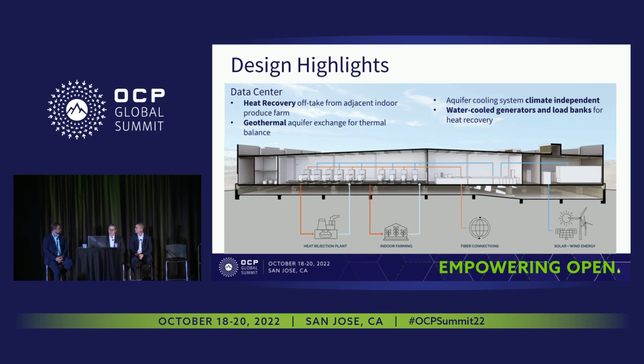That's governed by the Wyoming State Engineer's Office. The state of Wyoming adopted wholesale the EPA's guidance around Class 5 wells. Because it's a non-consumptive well, the permitting process is actually quite easy, since we're not appropriating any groundwater and sending it into the atmosphere or otherwise using it. It comes out of the ground, picks up heat, dumps some heat at the farms, and then goes right back into the same aquifer. That permitting process took us about 10 days.